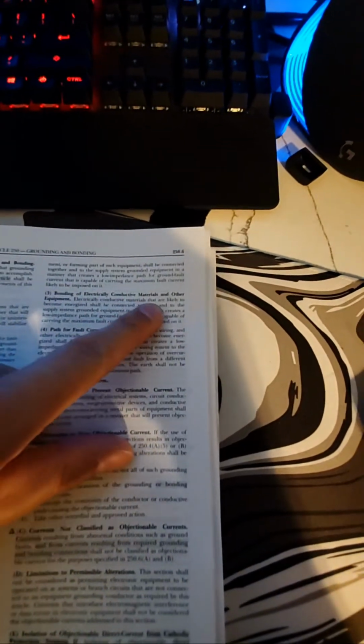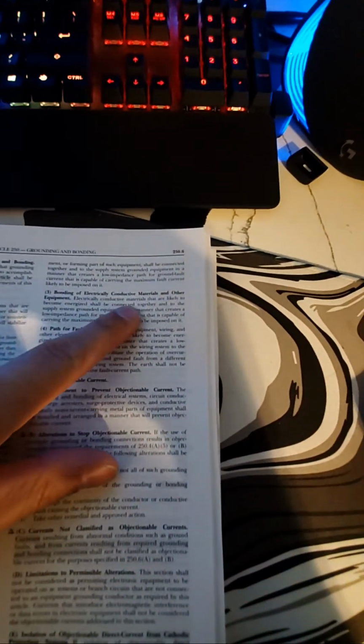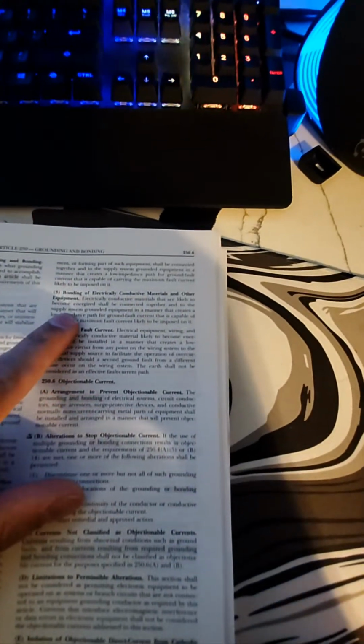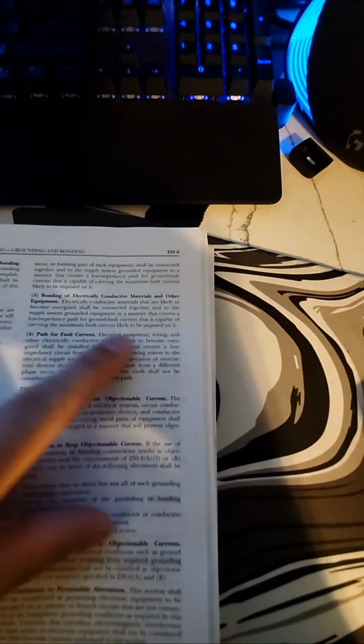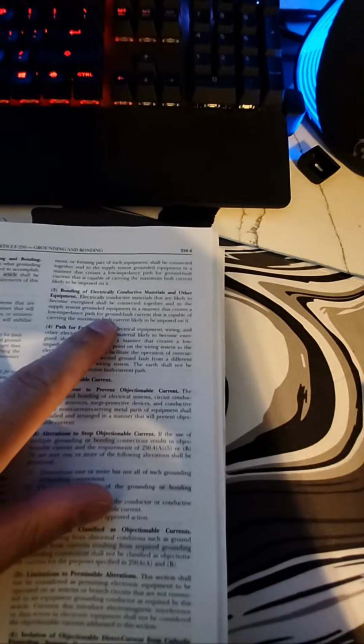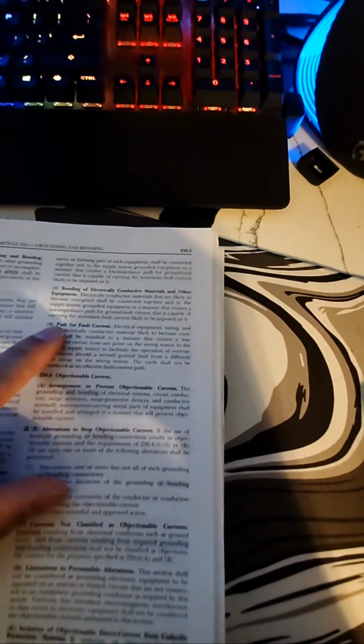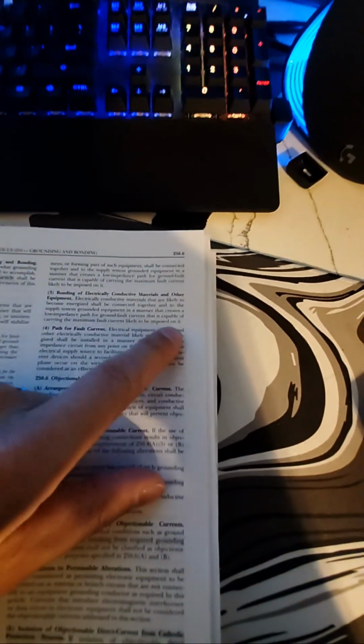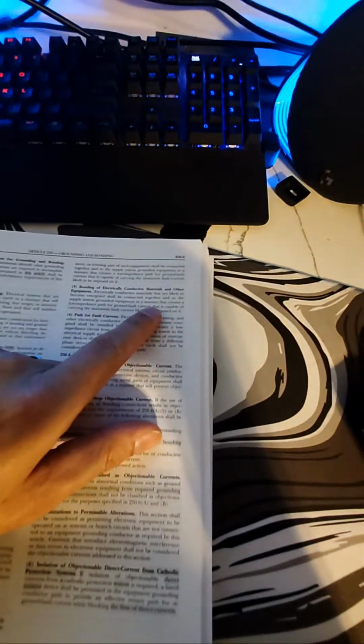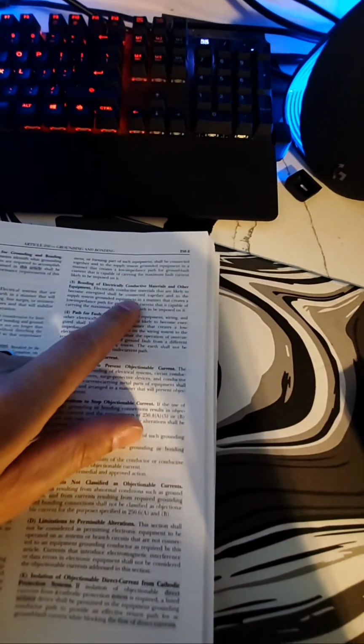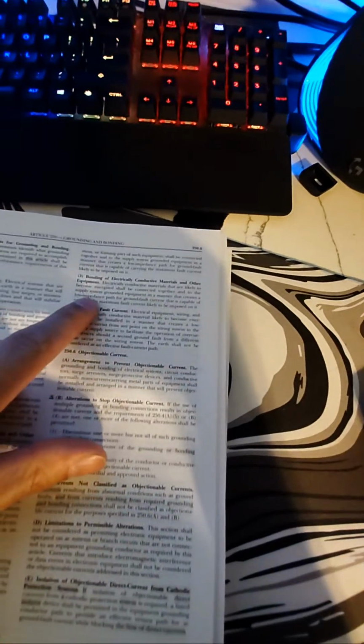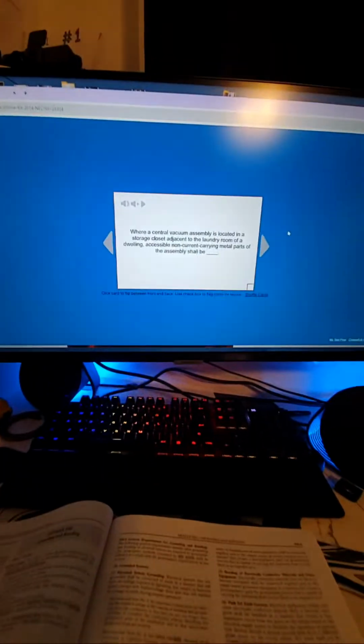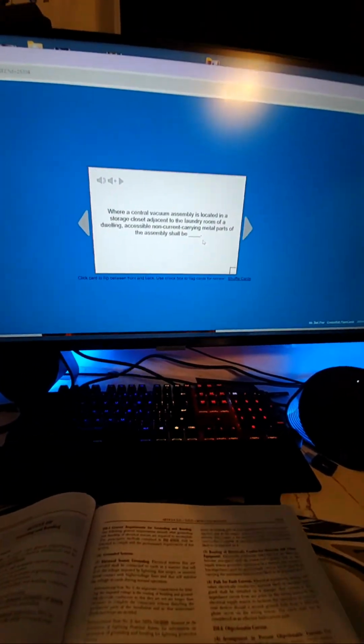Electrically conductive materials that are likely to become energized shall be connected together to the system grounded equipment in a manner that creates a low impedance path for ground fault current that is capable of carrying the maximum fault current likely to be imposed upon it. What they're doing there, where you're equipped in a manner that creates a low impedance path, that would be bonding. So we're just going to say bonded and see where they come up with so I can go to the next question. 250.4A3, let's see.